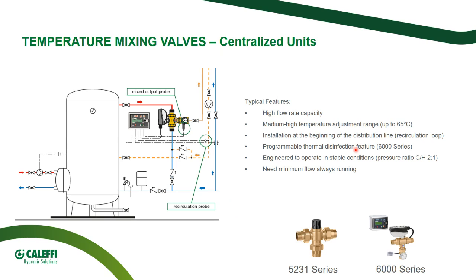So the first temperature reduction is done by a mixing valve at the point of distribution. Usually these kind of devices have high flow rate capacity. They have to manage the water flow throughout the whole system, so they have to have big Kv values. The adjustment temperature range is medium-high. We are speaking about up to 65 Celsius degrees. They are installed close to the generator or to the hot water storage, serving a recirculation loop, and they are connected also to the return pipe. We will see later in detail.